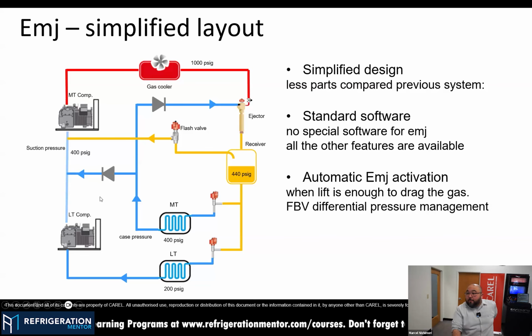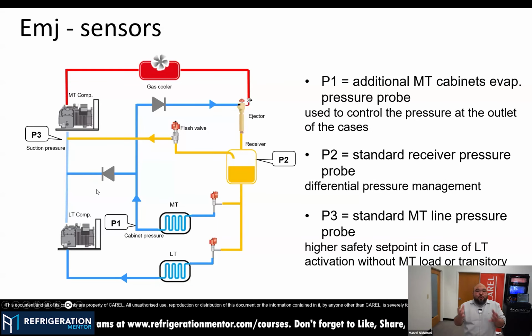Okay, so I showed you how it works on the mechanical side, but how does the control understand whether it can increase or decrease the pressure, speed the compressor up or down, and so on? How does this magic occur? This is done with the software, with the addition of just one pressure probe to what the standard system has. In a traditional system, you have a suction pressure probe connected to the MT line, which could be the same as the discharge LT pressure. We normally have this pressure probe controlling the compressors, and then we have the P2 pressure probe, the liquid receiver pressure probe, controlling the pressure and driving the flash gas bypass valve.